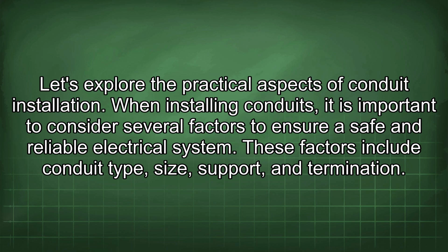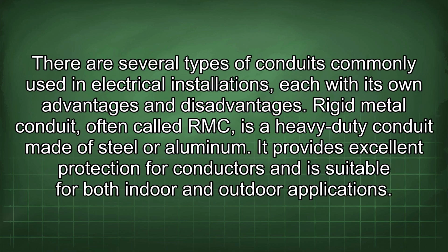When installing conduits, it is important to consider several factors to ensure a safe and reliable electrical system. These factors include conduit type, size, support, and termination. There are several types of conduits commonly used in electrical installations, each with its own advantages and disadvantages. Rigid metal conduit, often called RMC, is a heavy-duty conduit made of steel or aluminum. It provides excellent protection for conductors and is suitable for both indoor and outdoor applications.